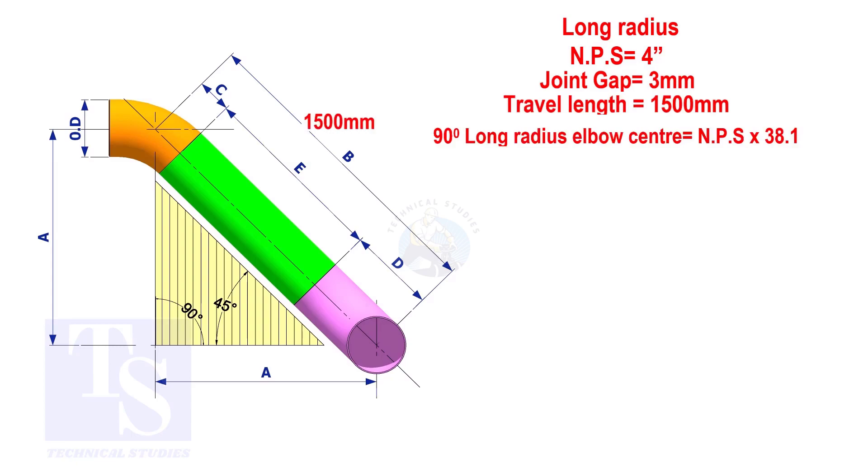The elbow center is the nominal pipe size multiplied by 38.1. So, the elbow center of the 90 degree elbow is 152.4mm.